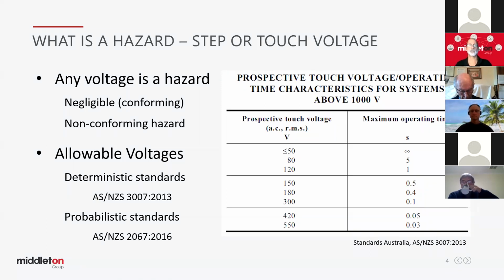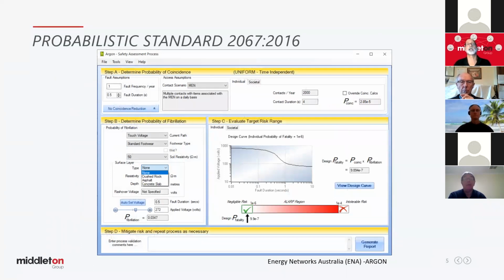And the most recently updated one, ASNZS 2067, updated in 2016. And on the next screen we'll be able to talk more about that one. So with a probabilistic standard, there are things that I just started to mention earlier, and you can see them on the screen here, top left: the fault frequency. How often does the fault occur on that system each year? How long is it on for before the fault is cleared?